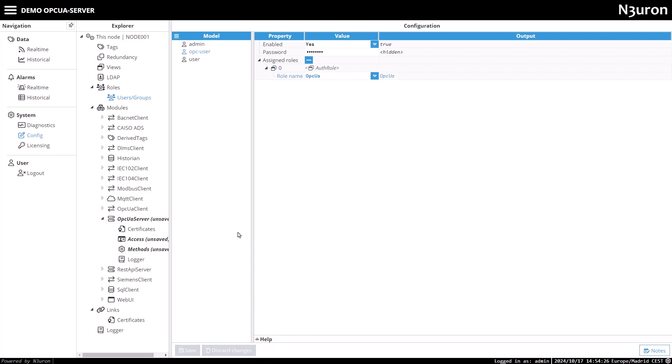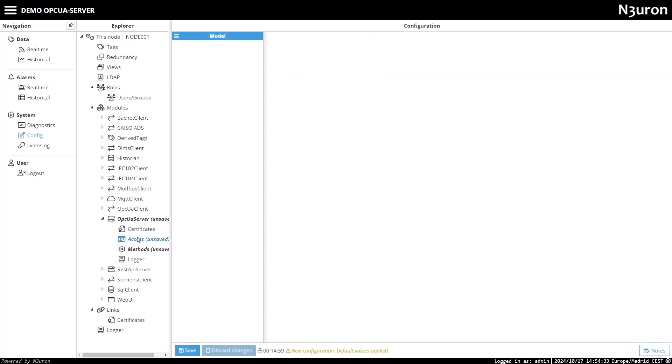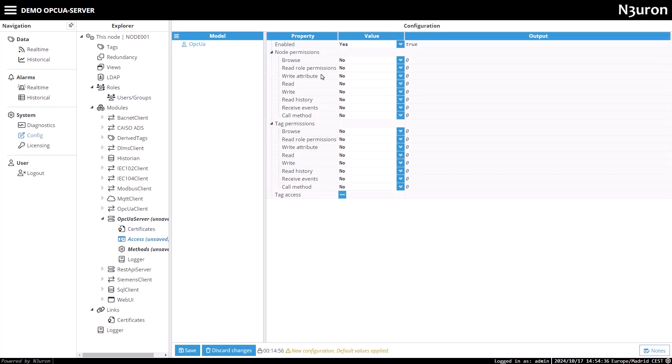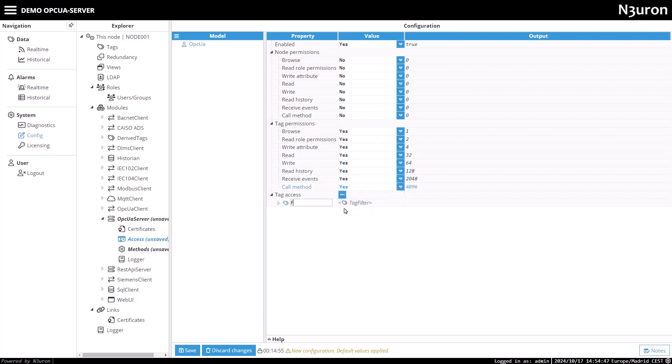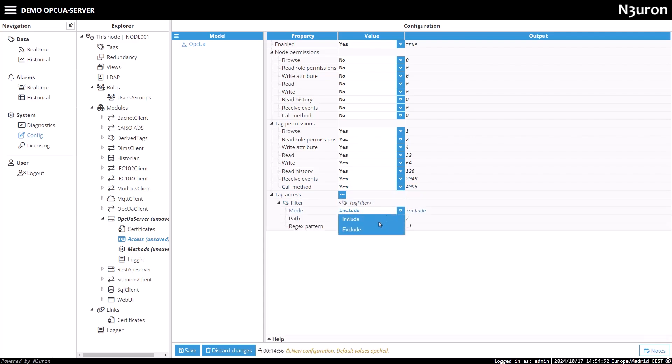Now let's configure the access permissions. I will grant only tag permissions in this example and apply an include filter to expose the entire data model to clients accessing with the OPC UA role. Remember, at least one include filter is required, though you can also add exclude filters to refine what is exposed.